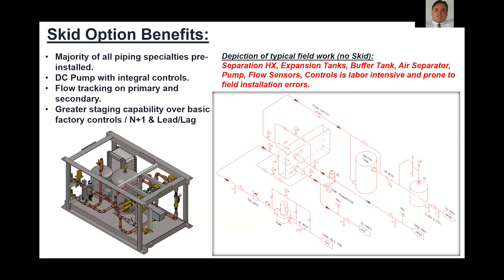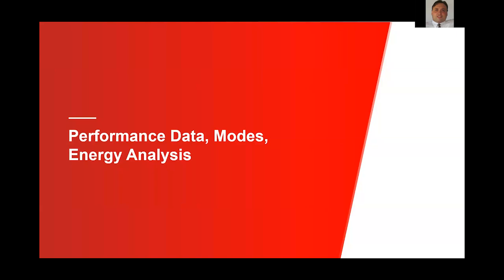So manufacturers are exploring and going to skid options. Mitsubishi's doing this. Other manufacturers have as well, to really encapsulate this entire scope on that primary secondary side into a single skid package with self-contained controls. Again, this simplifies the application. It also opens up some capabilities for greater staging, N+1 lead lag rotation type strategies, depending on the controls that this is paired with.